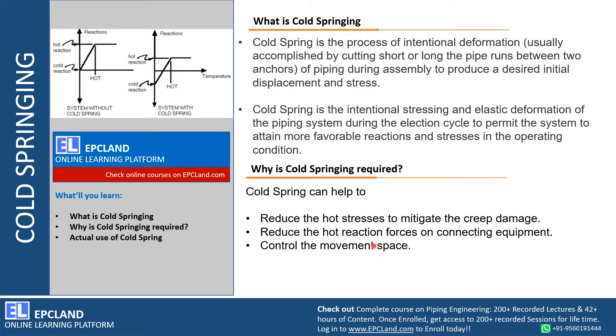It also reduces hot reactions. When connecting with equipment, there may be chances of hot reactions — these intentionally induced cold deformations will mitigate those hot reactions. When we know the system is going to move because of hot stresses inside the piping system, we provide this intentional deformation in advance so that the movement is controlled. This is what cold springing is and why we require it.